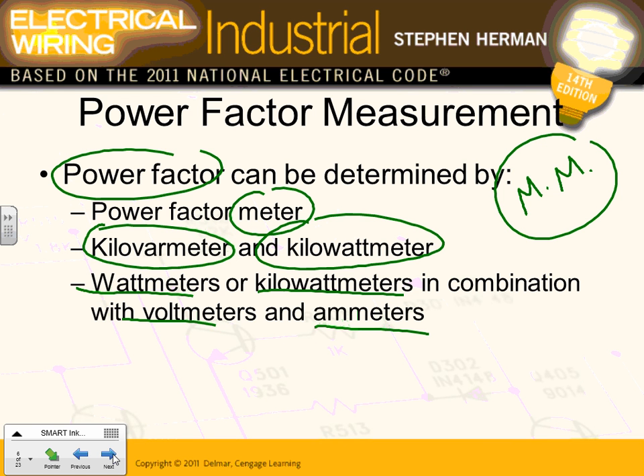Not a meter, it's a function in a multi-function meter. One big digital meter that can give you multiple things. Among them is the power factor. Any comment, guys, about how to measure it, at least being able to measure it? I will remind you, to find your power factor, what you need is kilowatt over kVA. If you were able to measure your kilowatt, and if you were able to calculate your kVA, then you can find your power factor. Any comments, guys, about measuring and or calculating your power factor?